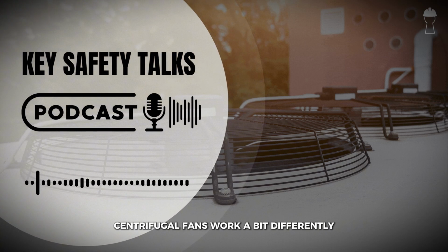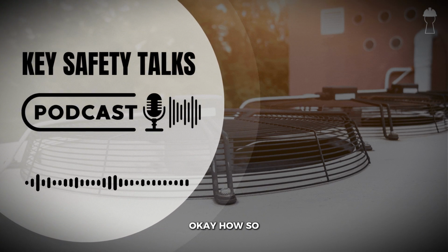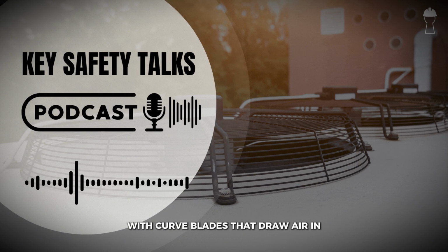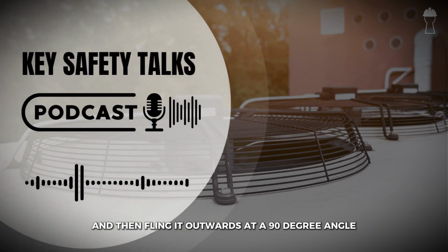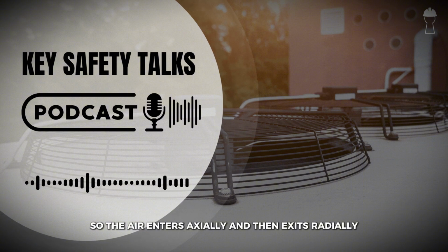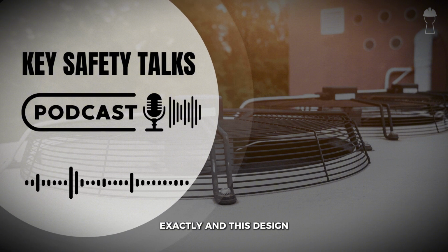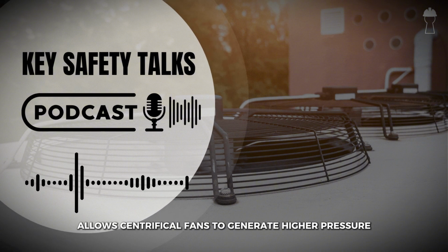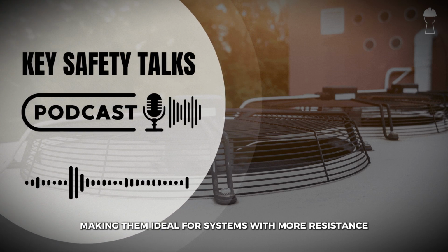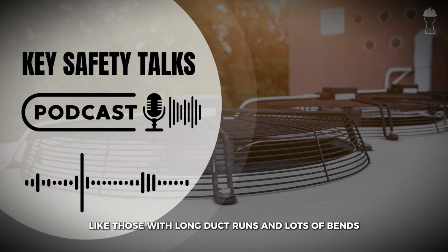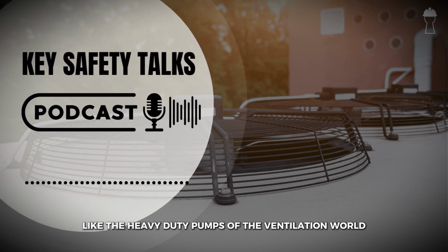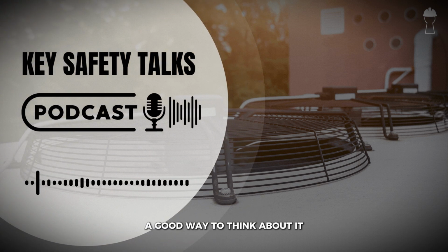Exactly. Now, centrifugal fans work a bit differently. Okay, how so? Well, they have a spinning impeller with curved blades that draw air in and then fling it outwards at a 90-degree angle. So the air enters axially and then exits radially. Exactly. And this design allows centrifugal fans to generate higher pressure, making them ideal for systems with more resistance, like those with long duct runs and lots of bends. So they're kind of like the heavy-duty pumps of the ventilation world. A good way to think about it.